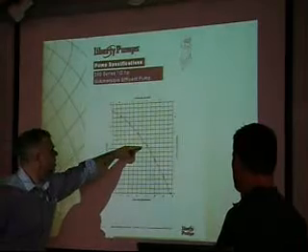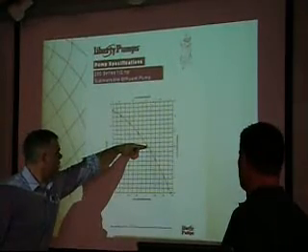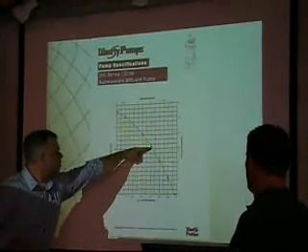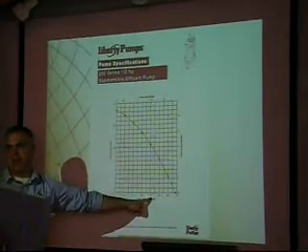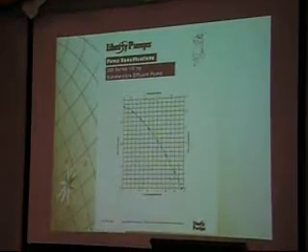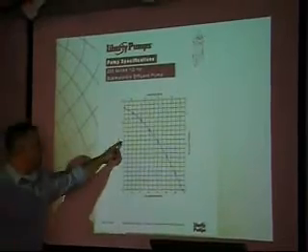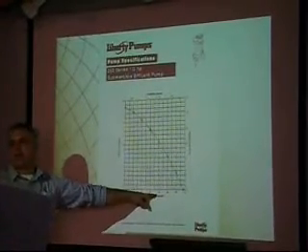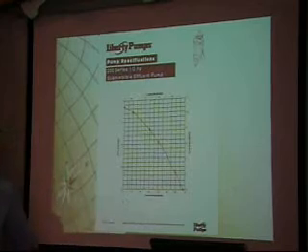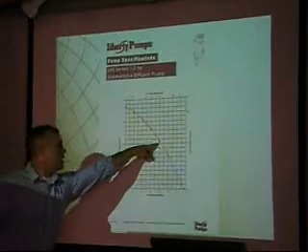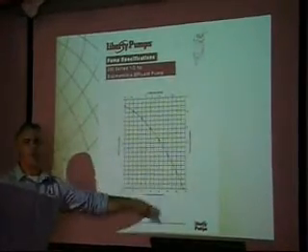Slide over here. And if we go about here, this pump that he's chosen is capable of producing 40 GPM at 21 feet of head. We only need 30. The pump's good to go. You can be over, you just can't be under. We don't want a pump curve that's down here, because it's either going to dribble out or never make it there. Make sense? At 21 feet of head, it's capable of doing 40. As long as you can do what's needed, and that's this, you've got the right pump.